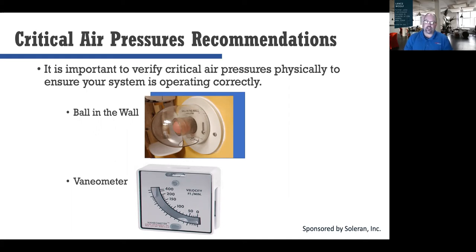One specifically that I remember is that there was a pitot tube failing, sending back false indicators showing that the OR room was negative when it was actually positive. So one thing I recommend is that you build into your PM program an auditing system specifically for critical air pressures.